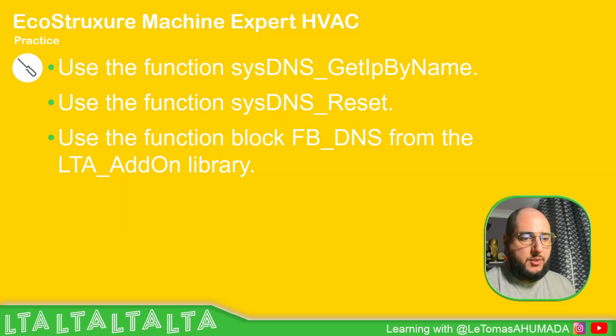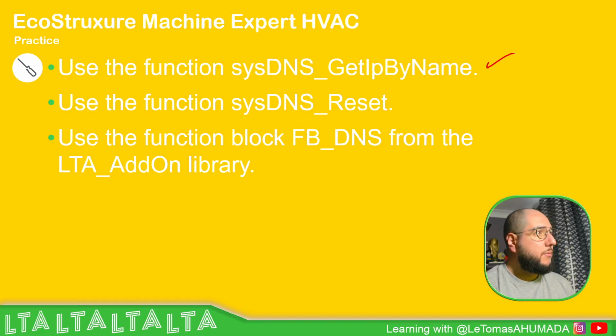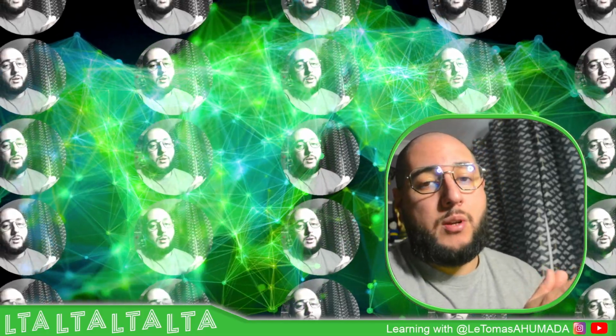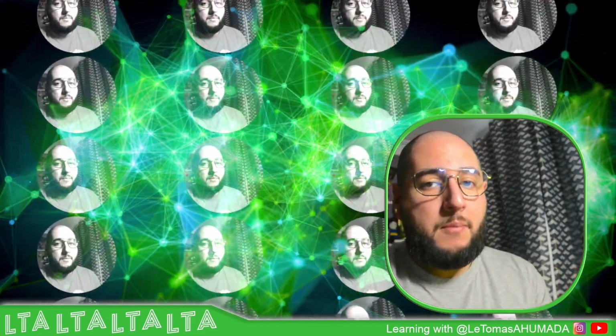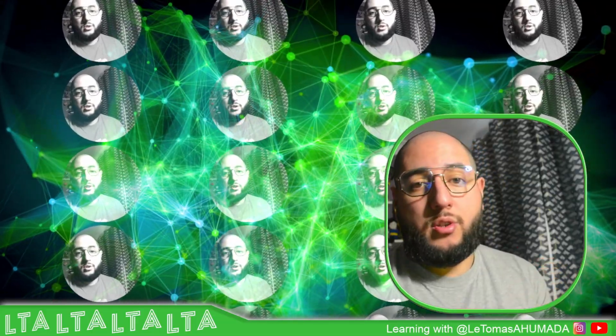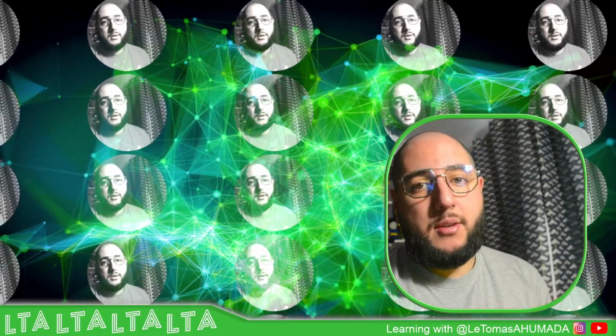So let's check if there's something missing. We already covered this part. Get IP address by name. Get the resets done, and also the FB DNS from my library, which is fine. So this is how you can use the DNS function. Basically, this DNS function will give us an IP address that we then need to use on the function block for the SMTP, that is the one that sends emails. So it's important. If you don't know the IP address of the server, then you just need to use the domain name to get the IP address. And if there's something wrong, then the block will tell you something's wrong.